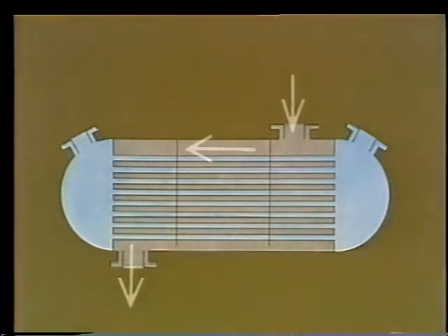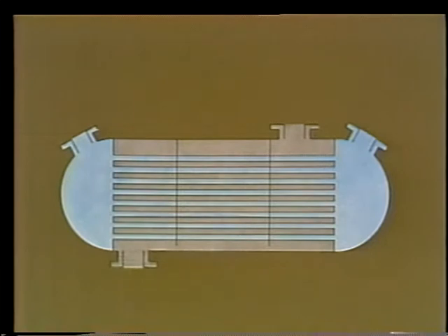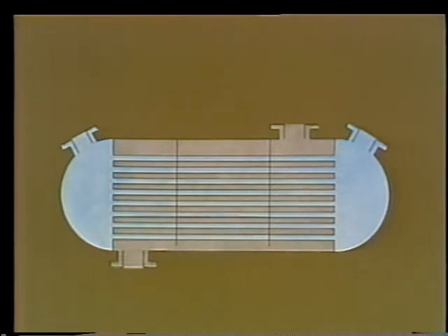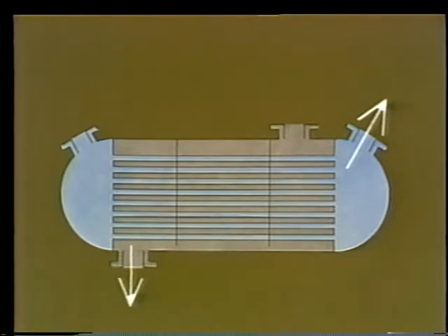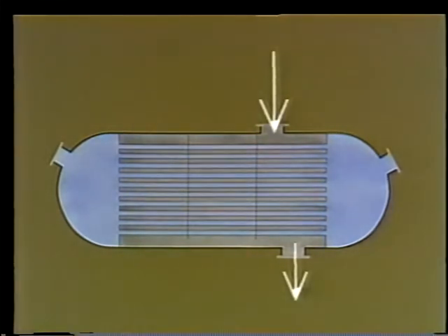Parallel flow means the fluid to be heated or cooled is flowing in the same direction as the cooling or heating fluid. In the counter flow type, they pass in opposite directions. The counter flow arrangement is more efficient because the temperature out of the cold fluid can actually be higher than the exiting temperature of the hot fluid, since a higher temperature difference is maintained all the way through. Cross flow is where the shell side fluid passes crossways over the tube bundle. Most condensers are cross flow.